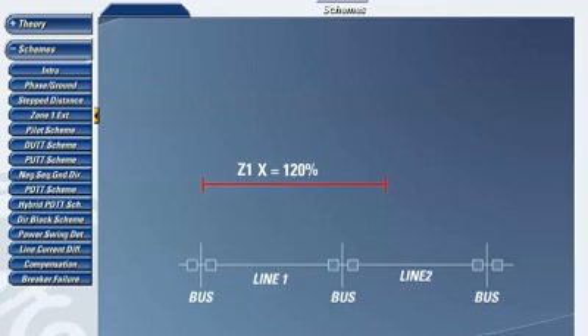This extended Zone 1 is used by the distance relay until it detects a fault within this zone of protection. Once a fault is detected, the relay will immediately trip the transmission line since there is no delay in the operation of the extended Zone 1 element. As you can see, the relay will trip the line even though the fault may exist in the area located in the extended Zone 1 but be in the adjacent transmission line.